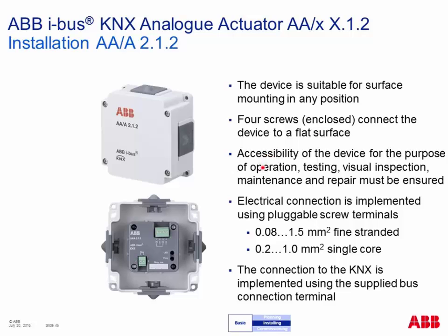So here it is also very important that the accessibility must be ensured, every time that we have access to the device, for example, for maintenance, for testing, or for measuring. And here we have other screw terminals, small ones, which are pluggable, and here it's limited up to 1.5 square millimeters for fine stranded, and up to 1.0 square millimeters for single core.